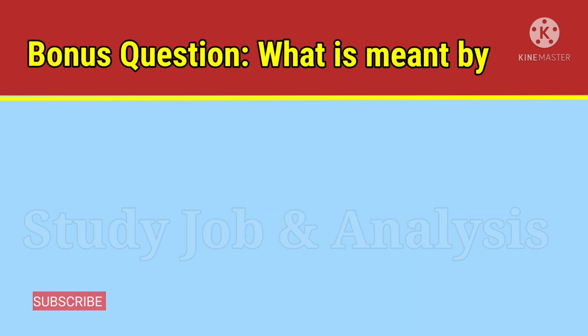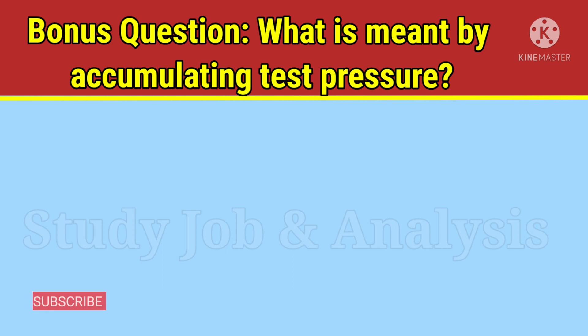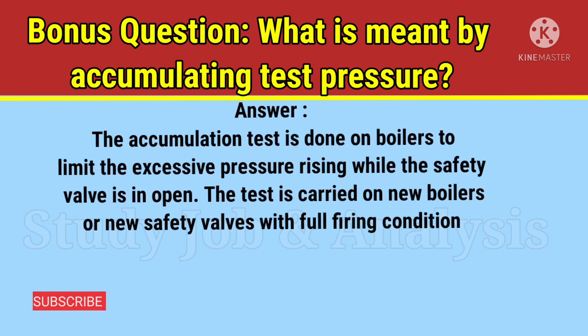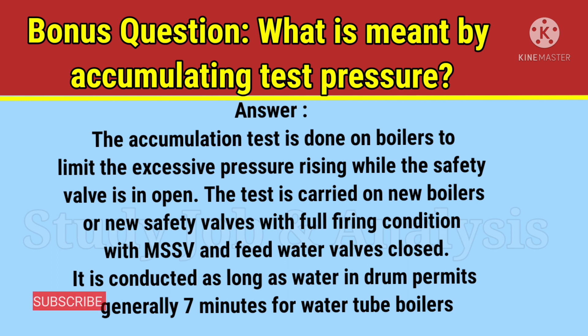Bonus question: what is meant by accumulation test pressure? Answer: The accumulation test is done on boilers to limit excessive pressure rising while the safety valve is open. The test is carried out on new boilers or new safety valves under full firing conditions with the main steam stop valve and feed water valves closed. It is conducted as long as water in the drum permits — generally seven minutes for water tube boilers.